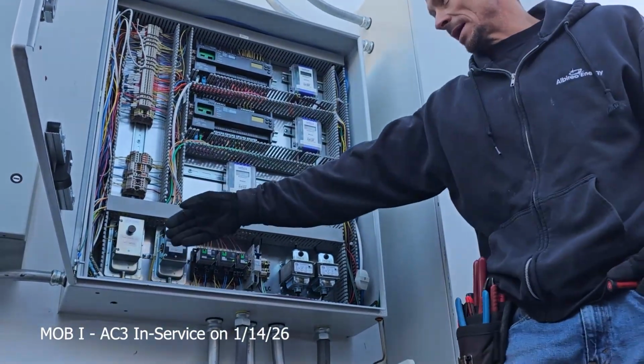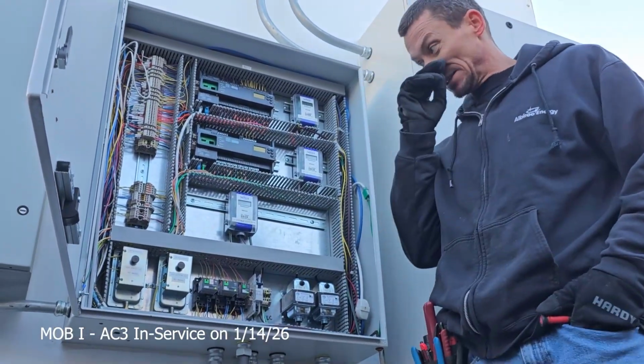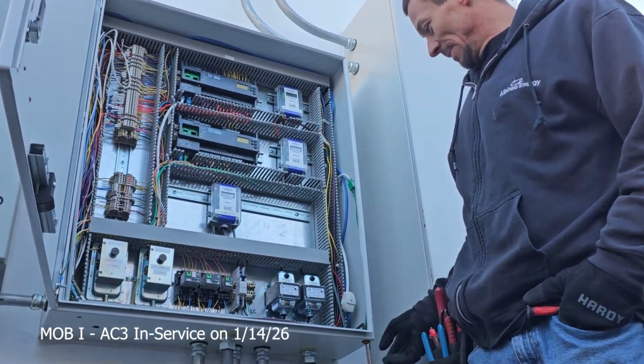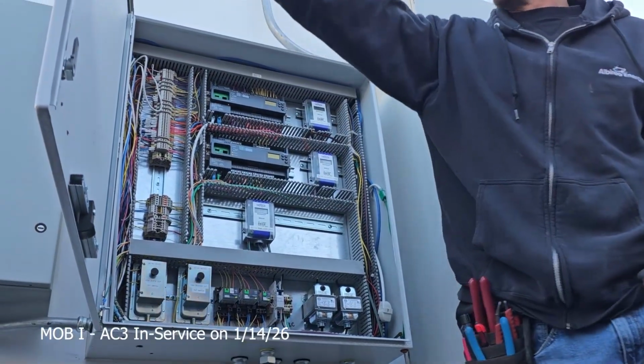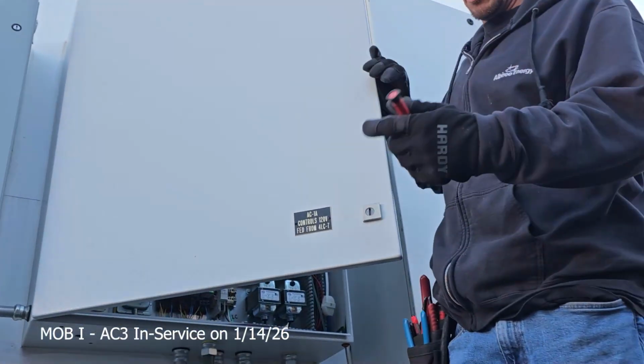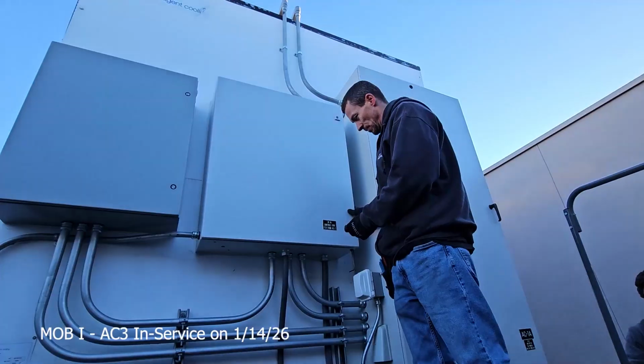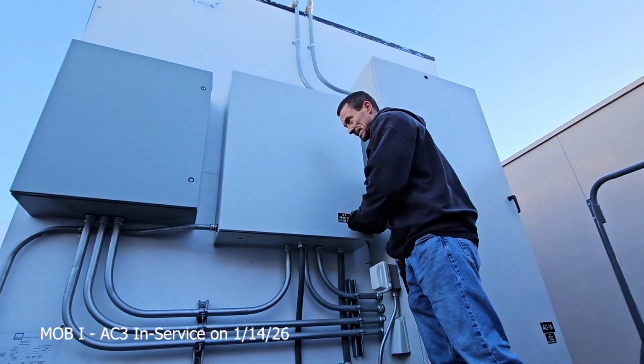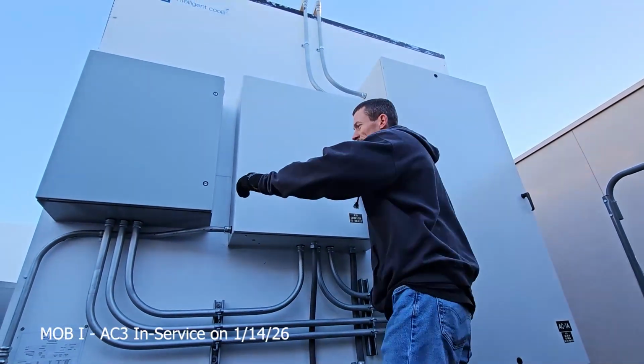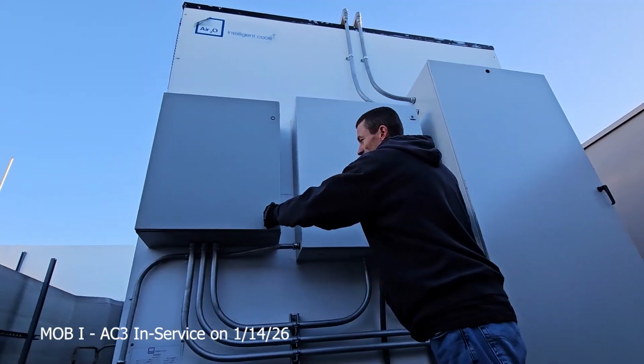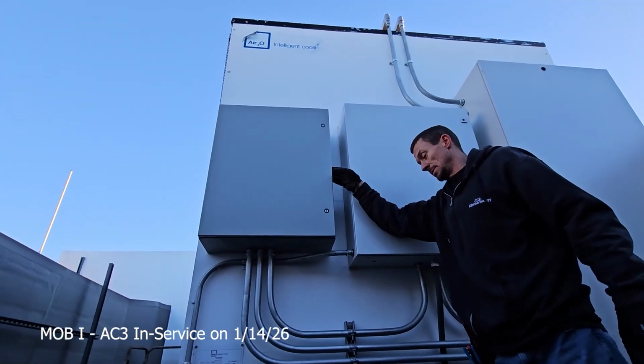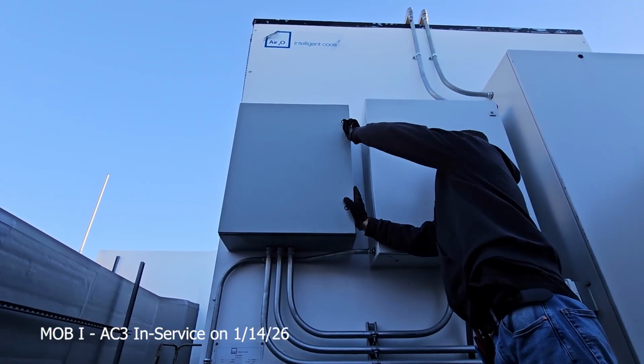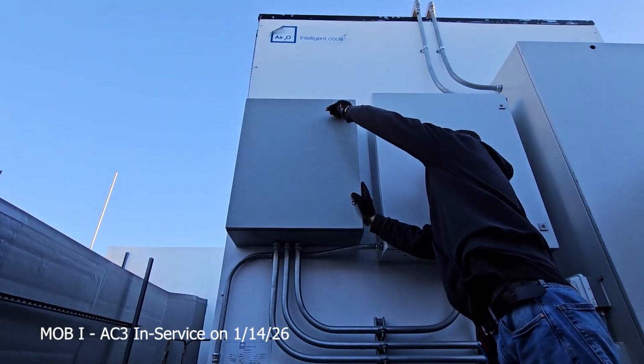Pressures, cut out, high suction, high static. So this is the outside air reference. And then I'll show you where the pickup locations are, if you guys want to see them, where the return static and supply static are. This right here you guys will probably not even care about, I'm sure, but this is the KW meter.